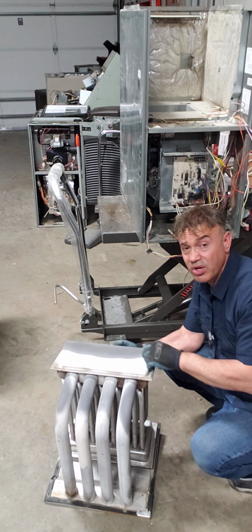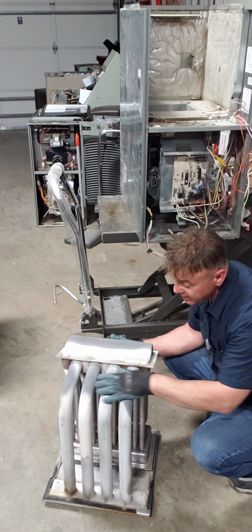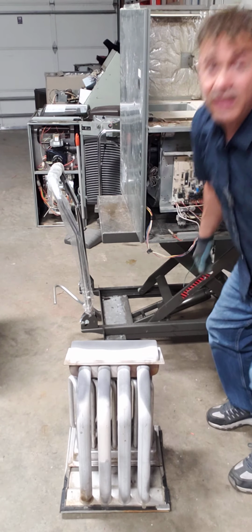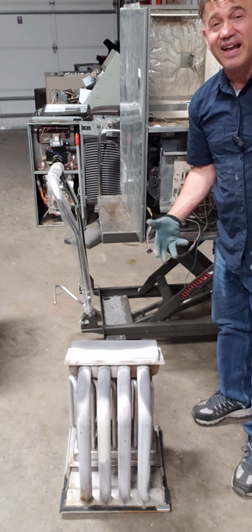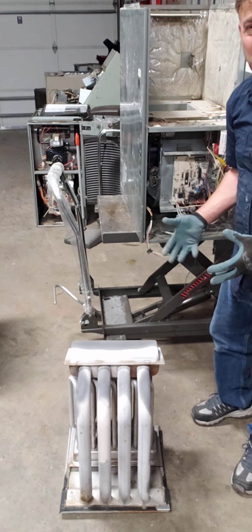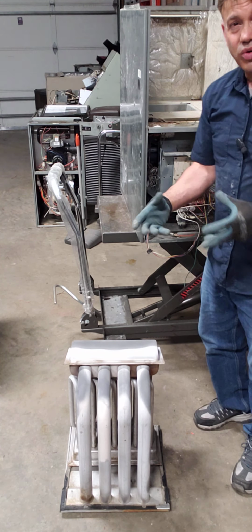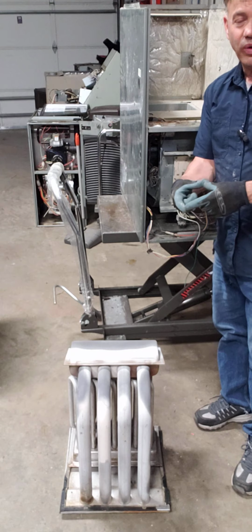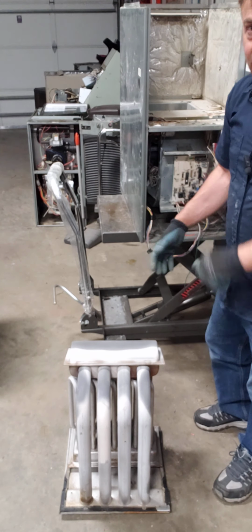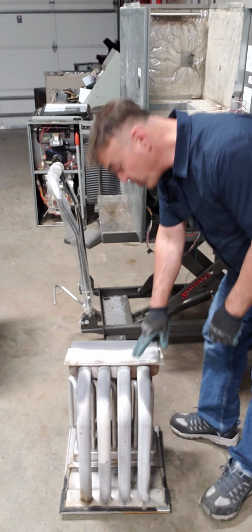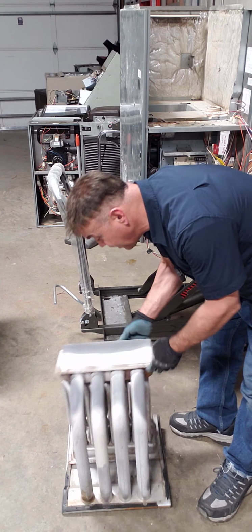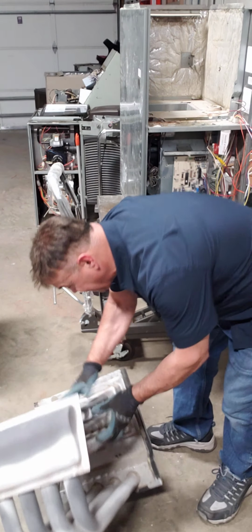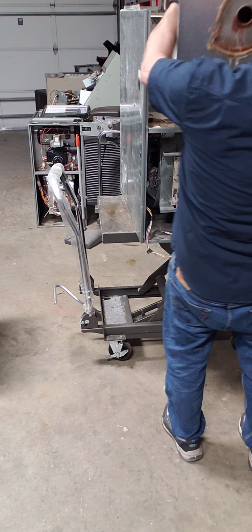Now, you see this mark here? These marks are telling me that the fire on this furnace was so strong from this gas valve. It's like you're cooking, as I told you, with a small two-egg pan on the biggest burner, and you open the gas all the way. You should never have these signs. Okay, so to put it back, it's basically the same thing. You carry it like this, right? And you put it back.